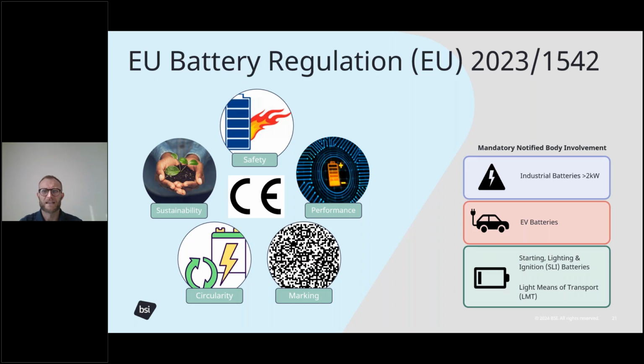Thermal cascading is where the thermal event of one battery then compromises the separating layers of adjacent batteries, leading to short circuits, spots where there's huge high resistance as current surges from the anode to the cathode, and then spot heating results. The separator between the cathode and anode can be affected at temperatures as little as 100 degrees, and as each cell affects the next, like a domino, it creates that domino of explosions.